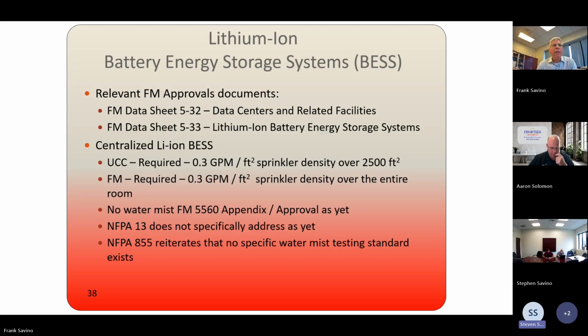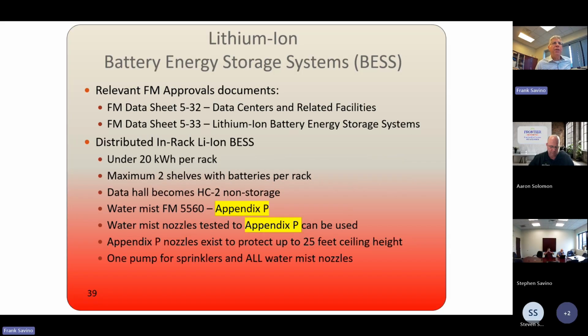Gotcha. So if the cabinet meets 9540A, then you can avoid the spacings required in NFPA 855. Okay. So right now we're talking about what you see on your screen, centrally stored lithium ion batteries. There are certain requirements on that, and there is no water mist standard approval for that hazard. But UCC is 0.3, FM is also 0.3, just the density is different. So this is lithium ion battery. Basically, this refers to in-rack lithium ion, right within your server rack.